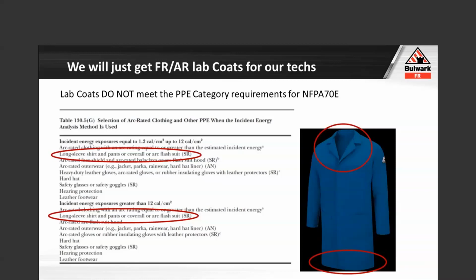Right in and around the chest area. At the bottom, it's wide open. If we happen to have an arc - and arcs are unpredictable, yes I just said there's a good chance they'll hit you in the chest - but what if it goes rocketing down to the floor, mushrooms out at my feet, and all that energy travels up the legs of my 100% cotton, aka candlewick, pants? I've just ignited my pants. I've just ignited myself from the ankles on up. Is that coat even going to have protected me?